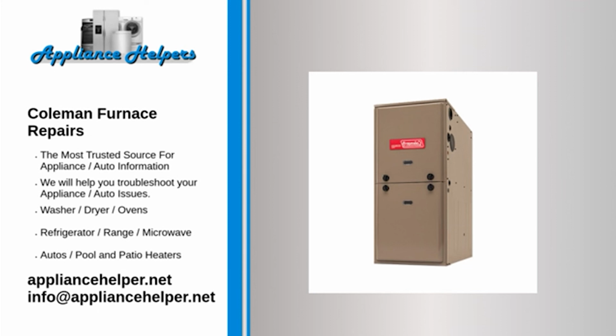Coleman furnace blower runs all the time. The control board has relays that regulate the voltage to each component in the furnace. If the relay that controls the blower motor fails while it is closed, it will send continuous voltage to the blower motor, causing the motor to run continuously. If the control board is at fault, replace it.